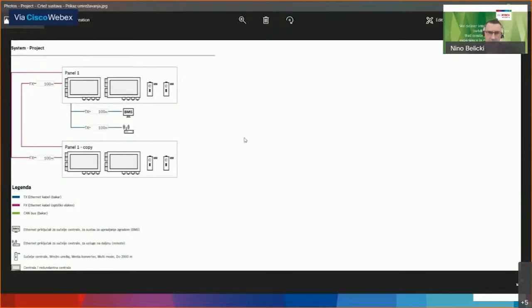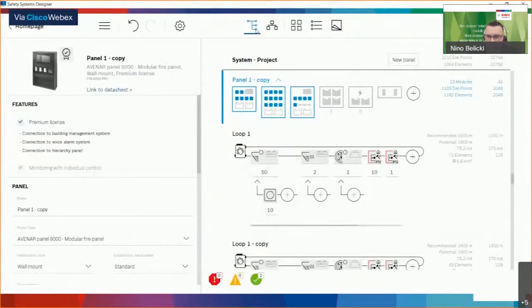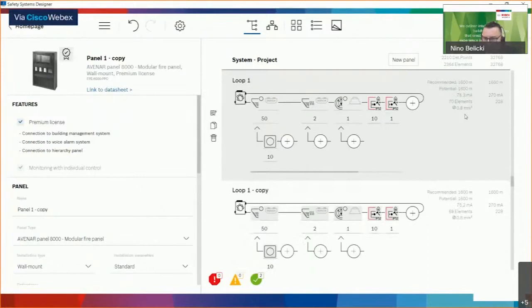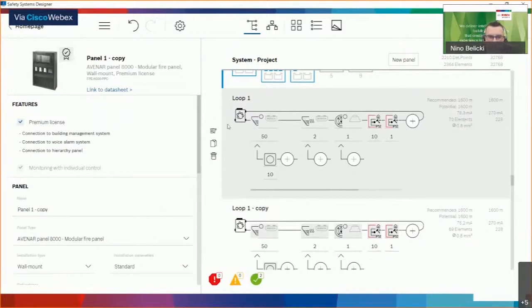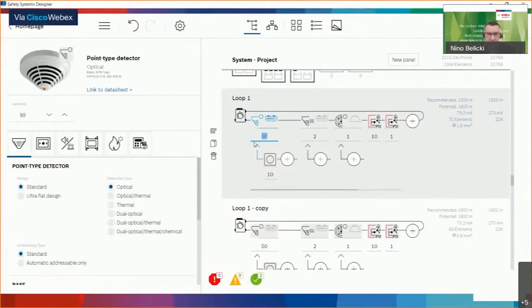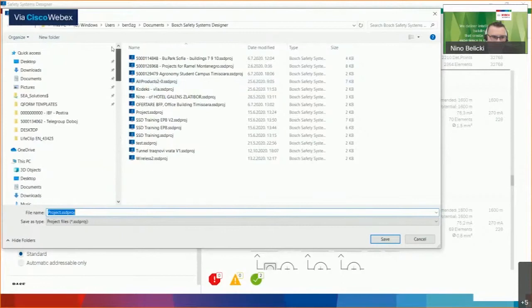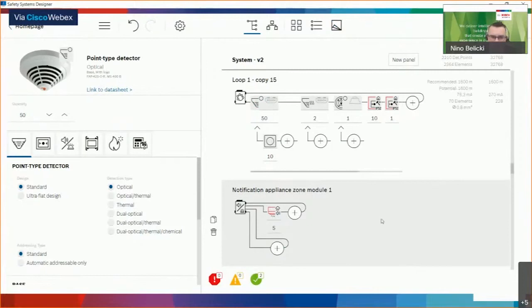So in 15 minutes, we managed to prepare a specification which is fully operational. You can always control loop length here according to cable diameter and load. This is the load, this is the number of elements. If you want to change something, you can always go back — for example, use thicker 1.5mm cable and make other adjustments. Then I can save as version 2. I can send this file to anybody who can start or continue working on the project. I think we are out of time for the safety part — please contact me or Florin Booker for safety systems whenever you need. I would now like to give the floor to colleague Florin to present the BIM modules.